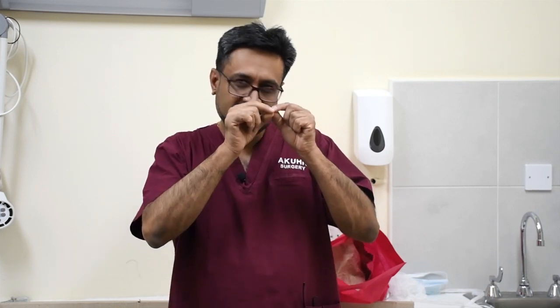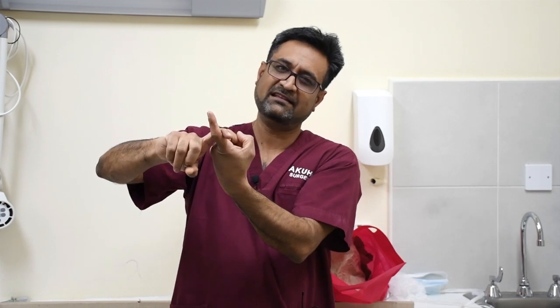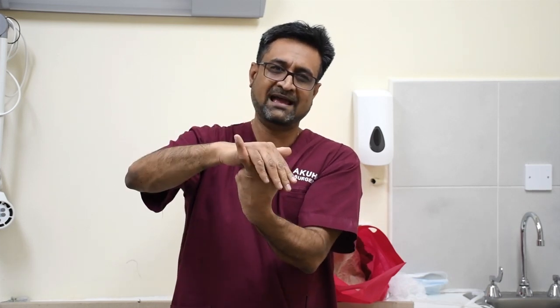The electricity has to find a way back to the return electrode, wherever we put it, so we'll demonstrate. But as it finds its way out there, when it reaches a thin spot, it heats up there. So if that thin strand is attached or hooked onto, let's say there's a band this way and the thin strand is attached to bowel and the bowel loop is lying on it, it will hit here. So you're burning here, but it will hit here. And it will cause a burn on a bowel loop that was way away from your site of operation, making it very dangerous. So that is very important to understand.